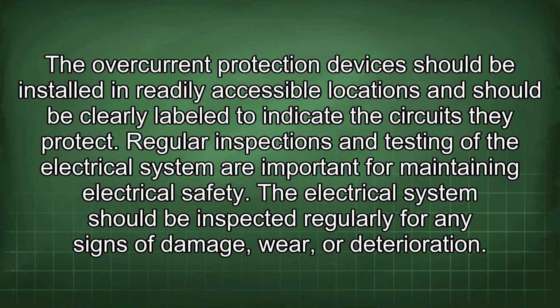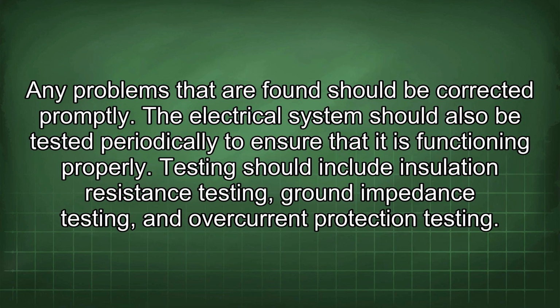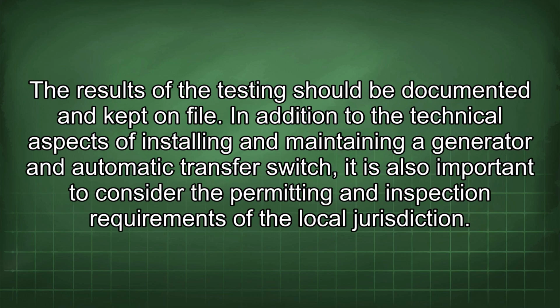The overcurrent protection devices should be installed in readily accessible locations and should be clearly labeled to indicate the circuits they protect. Regular inspections and testing of the electrical system are important for maintaining electrical safety. The electrical system should be inspected regularly for any signs of damage, wear, or deterioration. Any problems that are found should be corrected promptly. The electrical system should also be tested periodically to ensure that it is functioning properly. Testing should include insulation resistance testing, ground impedance testing, and overcurrent protection testing. The results of the testing should be documented and kept on file.